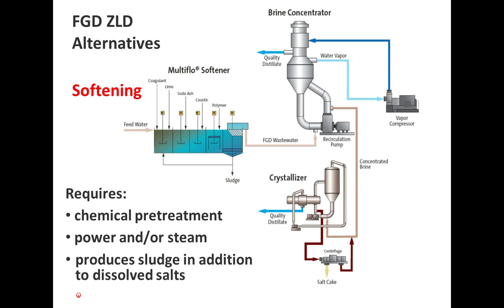The first one, as I said, is to soften the FGD wastewater using lime and soda ash. Lime precipitates out the magnesium as magnesium hydroxide. Soda ash precipitates out the calcium as calcium carbonate. Those are removed as sludge from the softener system. And then the brine, which is left, is basically a sodium chloride solution, and that goes to a conventional evaporator and crystallizer. So we have a lot of chemicals required to do this scheme, and we also have a lot of sludge that we have to dispose of.